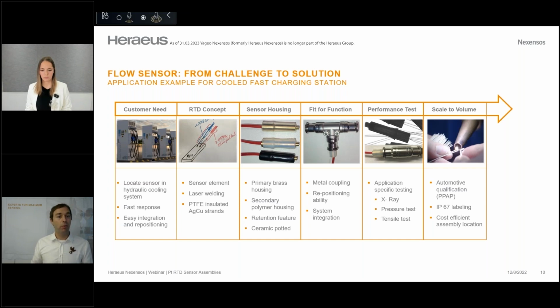So we decided for an M310 here, a very small one, because it needed to fit in small holes. We decided for laser welding to connect the wires in a sustainable way to the element. And we decided for silver copper strands and for a PTFE insulation to make sure that we have good electrical performance and that the insulation also will withstand higher temperatures. Next point, that was something that Charlotte was also explaining.